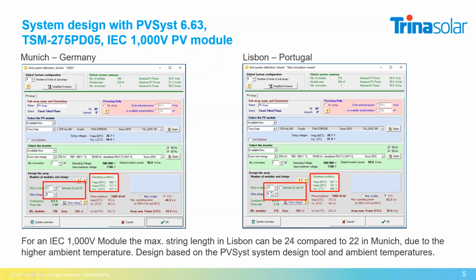But if I compare it with Lisbon, which has a higher minimum ambient temperature, you can see that the string length is 24 modules compared to 22 modules, which is already significantly higher. But you can also see from the inverter utilization that the VOC voltage is only below 1000 volt instead of close to 1100 volt, because the modules are only certified up to 1000 volts, and it needs to be avoided to exceed the 1000 volt certification.